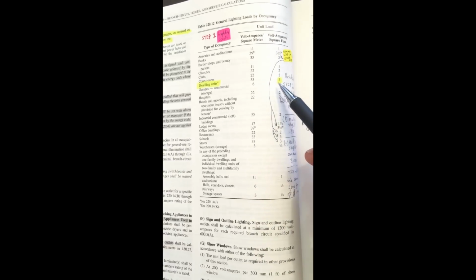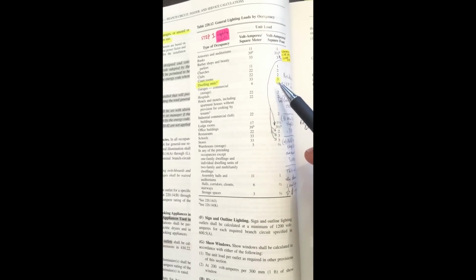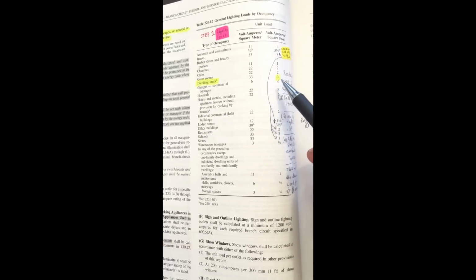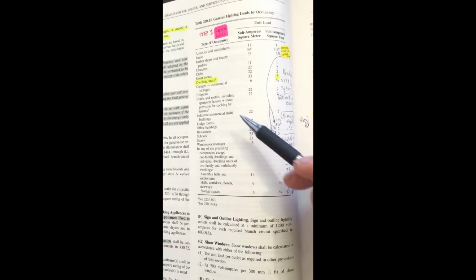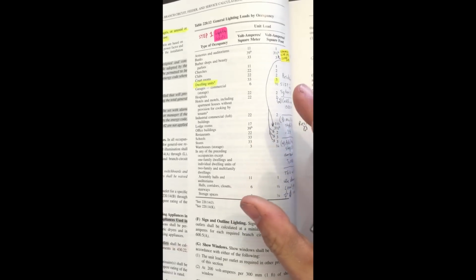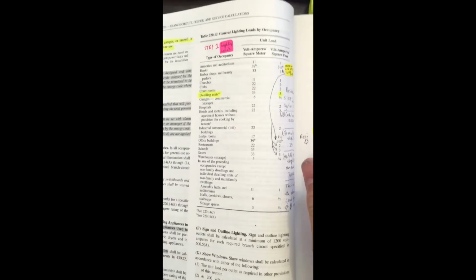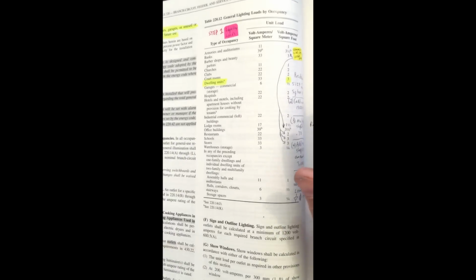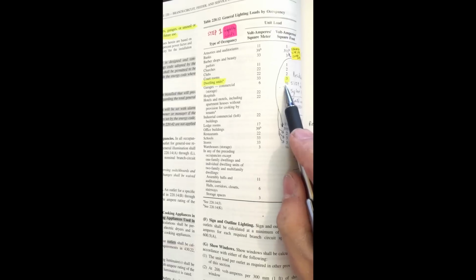The reality of it is, this number right here ain't never going to happen. We've got to figure out how to get this number, though, from a code calculation called a connected load, and that's what this is. This is a connected load, meaning that if everything that possibly could be on is on, that number would be what we're talking about.